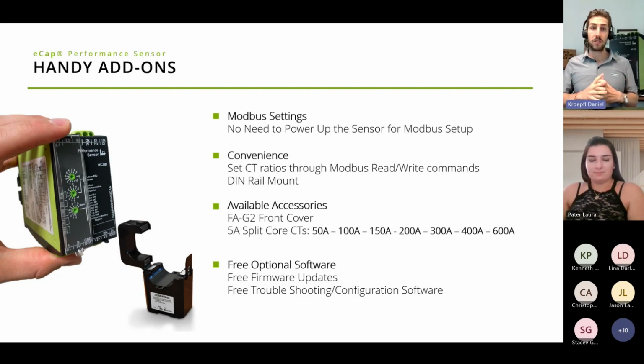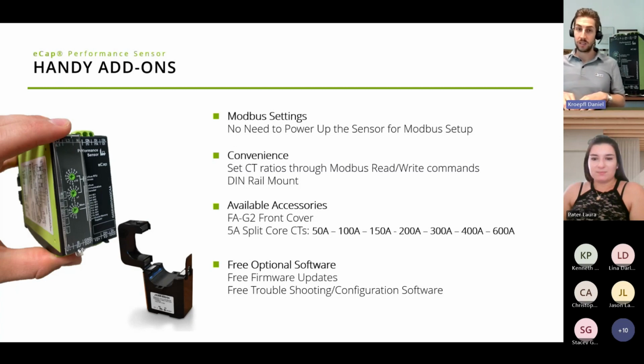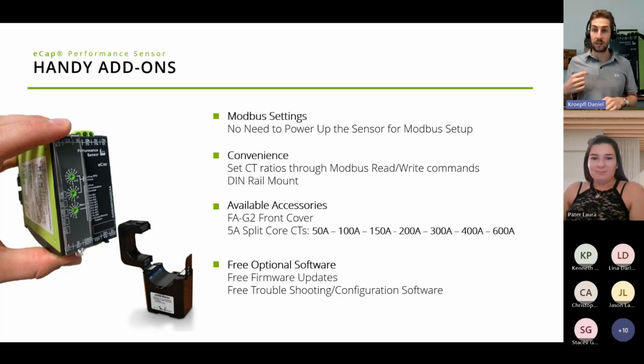Another thing we figured out over the past few months is a very convenient way to set current transducer ratios. That means you don't have to go into a software and adjust the ratios. What you could also do is just set the ratio through a Modbus command and then remotely reset the eCap performance sensor to take in that current transducer ratio.